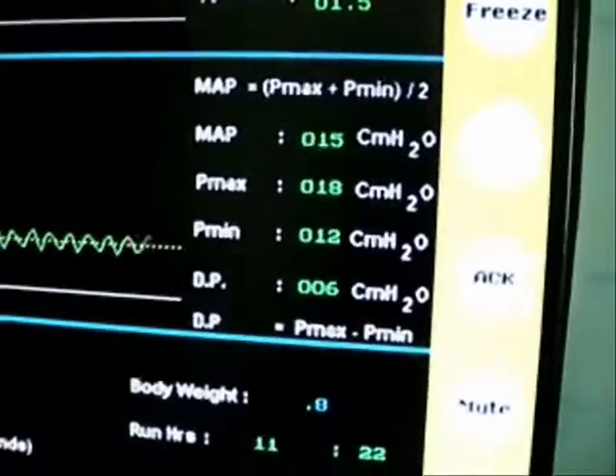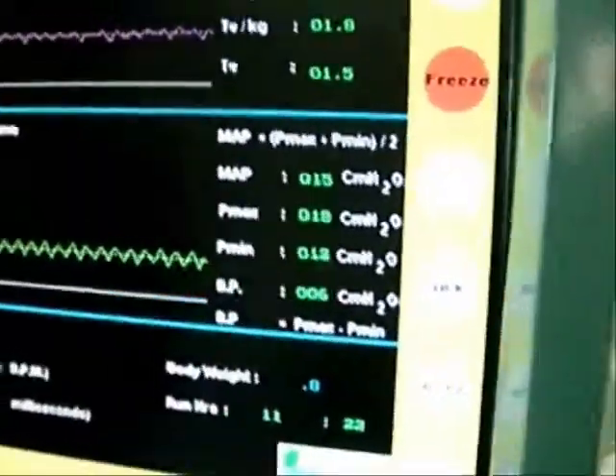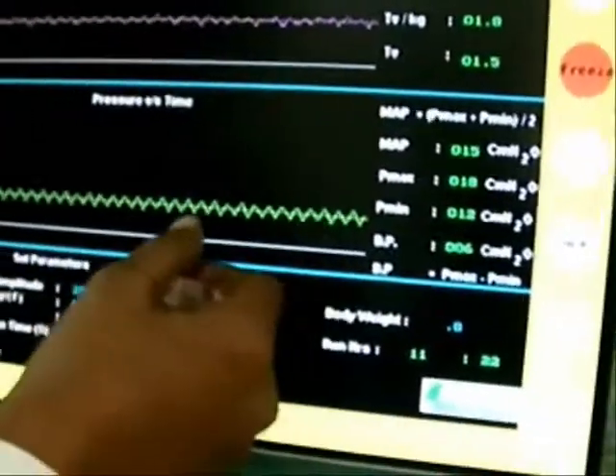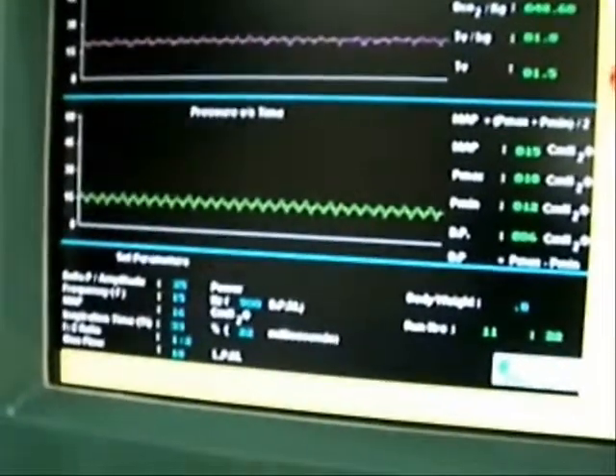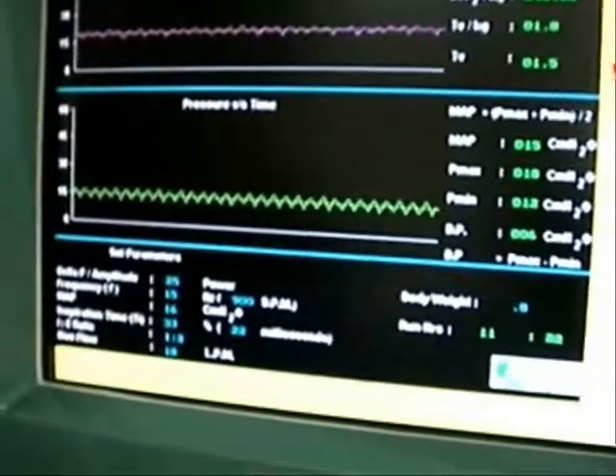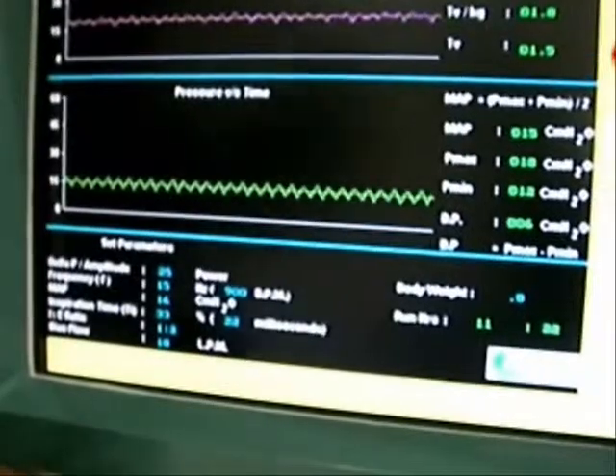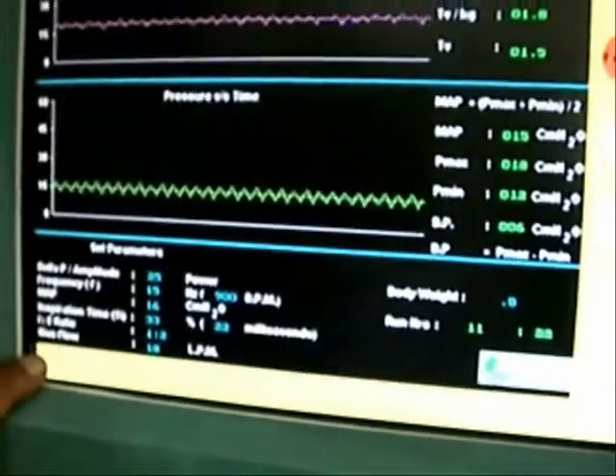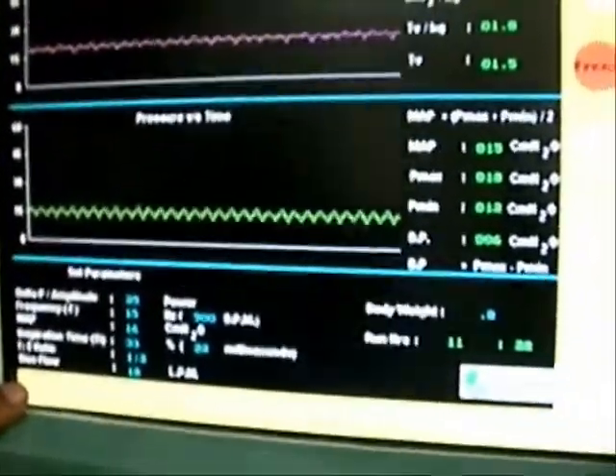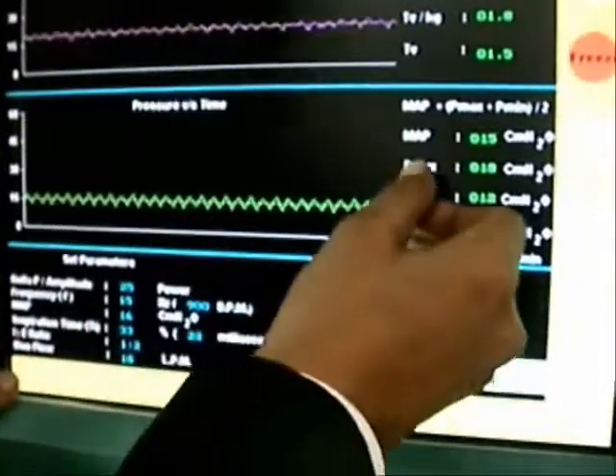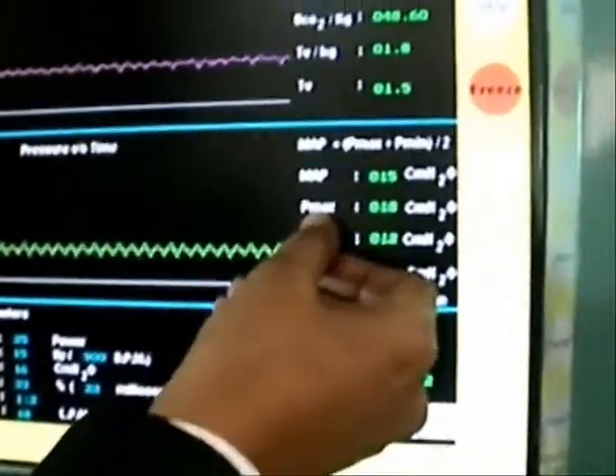Plus a few more features. You can notice here is the set MAP and here is the actual MAP that is delivered. Now how this MAP is calculated, I'll show you. I'll just freeze this graph for you. Now, this is the mean airway pressure. We have opened up the lungs, kept them open, and now we are imposing vibrations on the mean airway pressure. The maximum pressure generated during the inspiration phase is sensed and indicated as the maximum pressure, or the P max. You can notice it here. The P max here is 18 centimeters of water column.